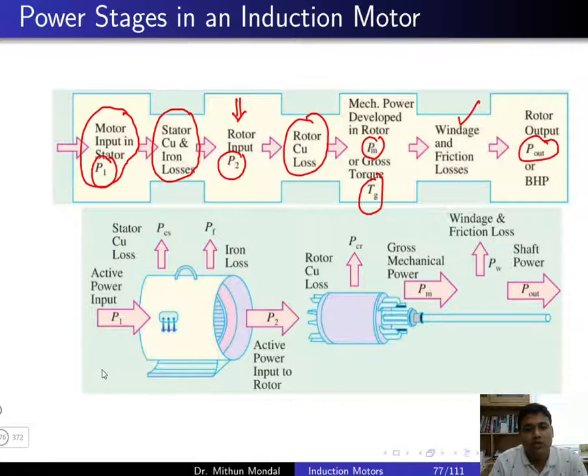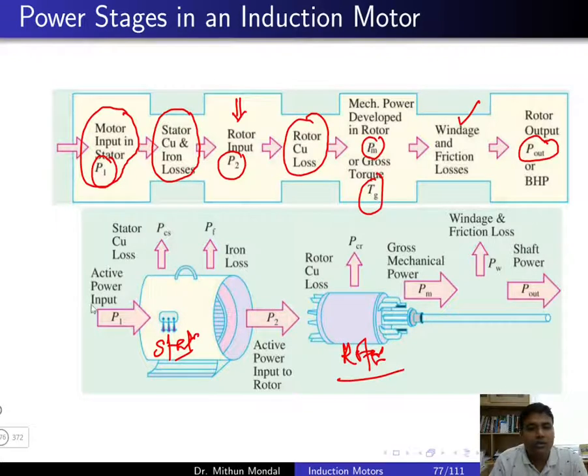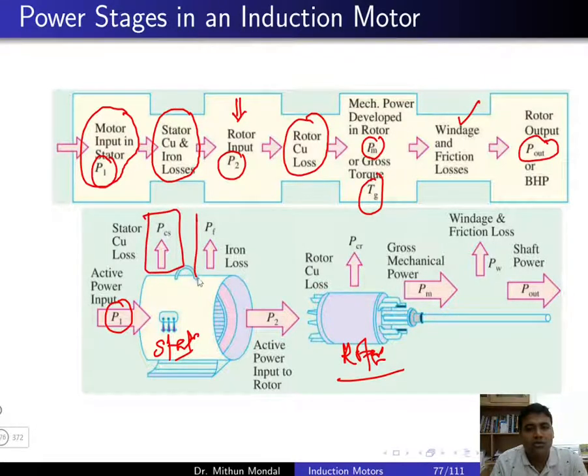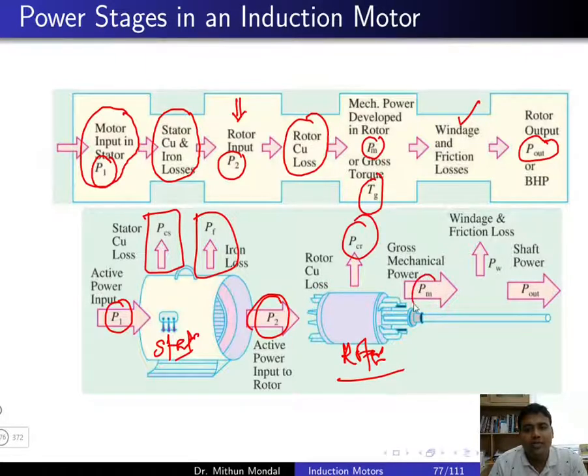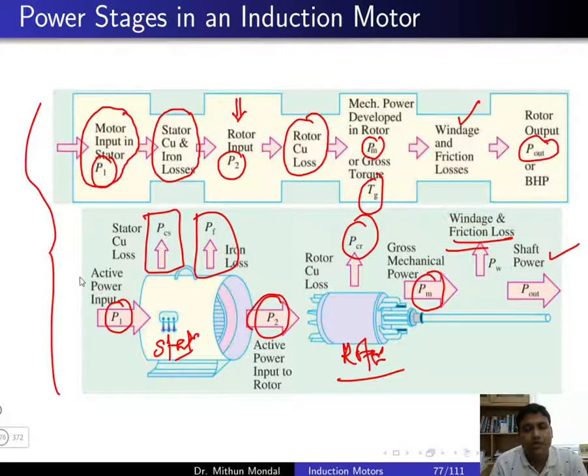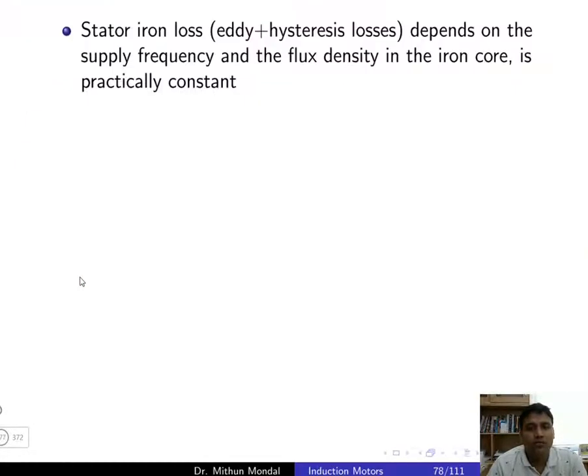Observing how power flows from input to output: this is your stator and this is your rotor. The power input P1 leads first to stator losses, giving us the rotor input P2. This rotor input then leads to rotor copper loss, and the output is the gross mechanical power Pm. Subtracting windage and friction losses gives the net shaft power output.